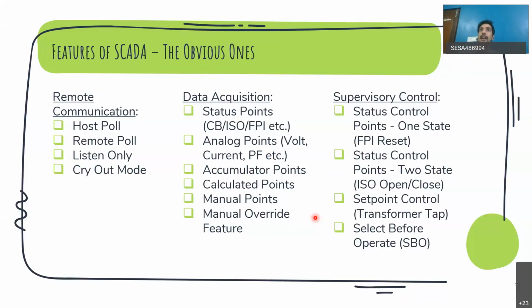Then manual points, so you don't have to have this communicating equipment everywhere in the field. So for example, there can be some substations or some RMUs where there is no remote communication enabled, but still you can manage them in the control center. Only thing is you cannot do any remote operations. You have to send someone from the field crew there and they have to manually operate. So once they operate it, that change will be manually reflected by you in the control center. So that is manual. With respect to status and analog points, whatever is happening in field is automatically reflected. Manual points, there is no communication, so you have to do it manually. But still you can manage them in the control center. And you have this manual override feature also.